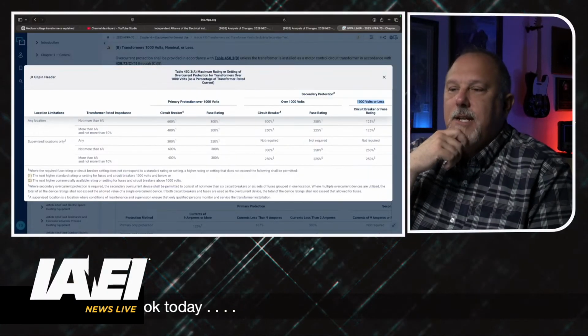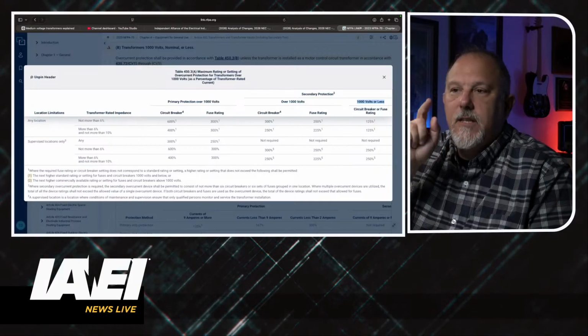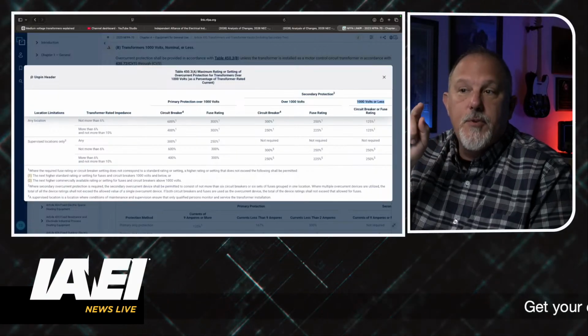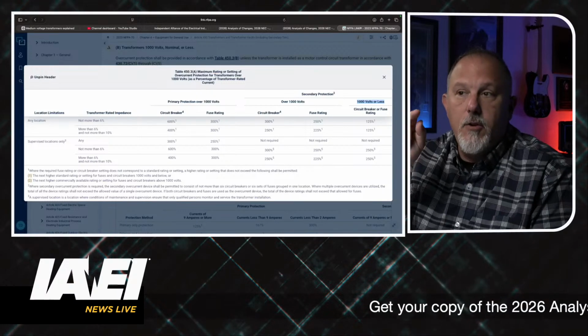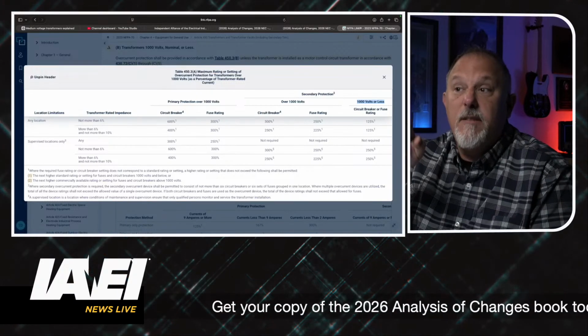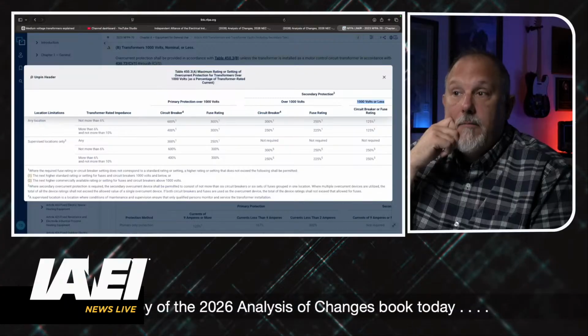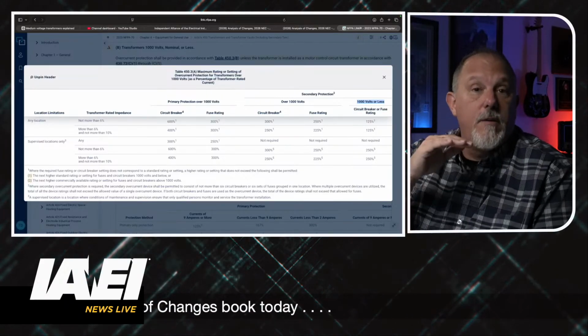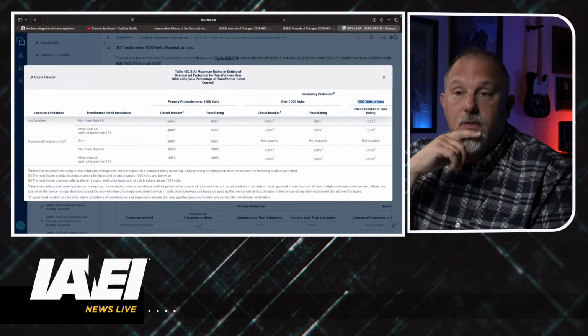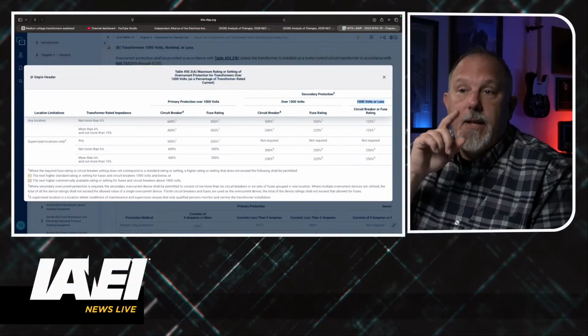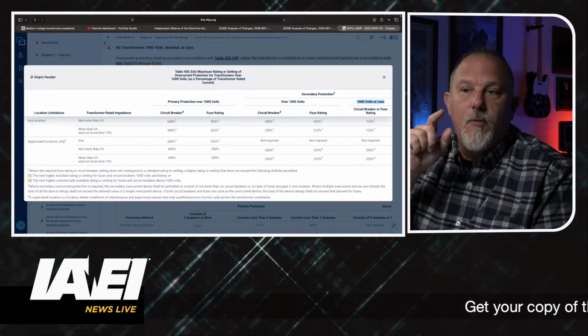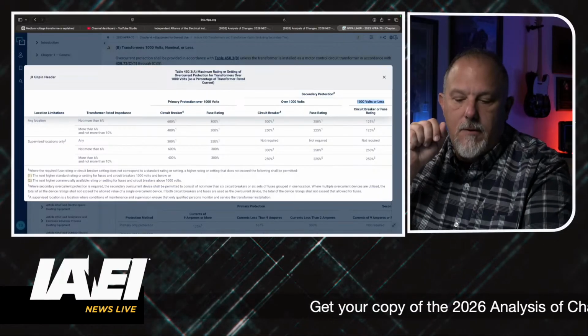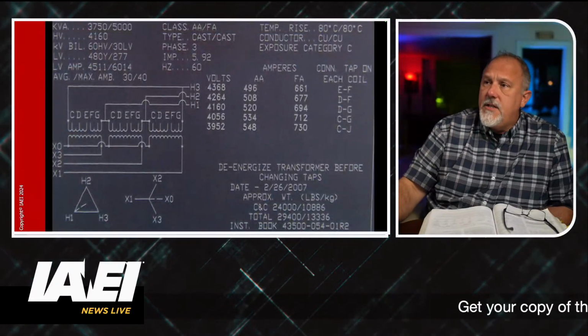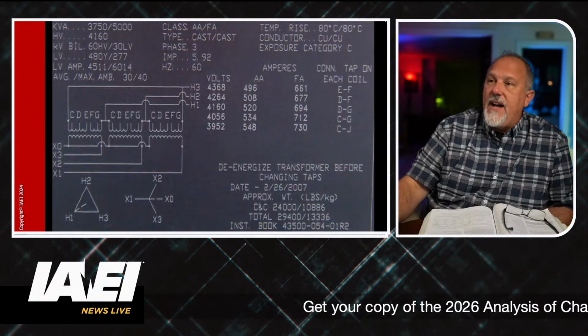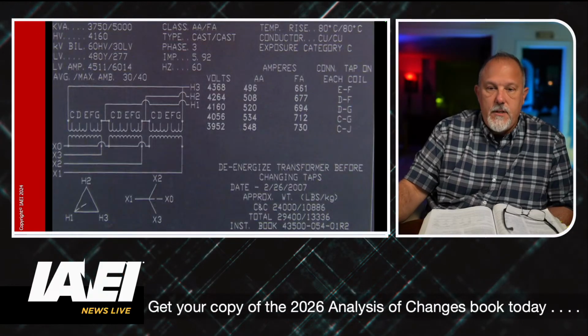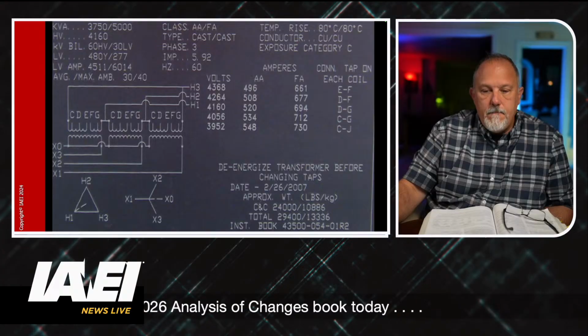But in any case, if you look at this table, it gives you the percentages when you have a circuit breaker or a fuse, because in many medium voltage applications, I may have a fuse rating, a medium voltage fuse protecting the transformer. And then they also key off of the rated transformer impedance. Now, on this one here, my impedance was 5.92%.